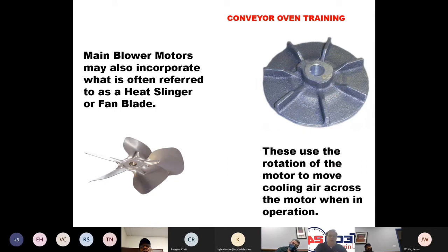Main blower motors are also going to incorporate what's referred to as heat slingers or fan blades. These use the rotation of the motor to move cooling air across the motor when it operates. So the fan blade on the bottom left is a fan blade that would mount to the end of a motor on a shaft, and as the motor turns, that fan blade is going to blow cool air across the motor.